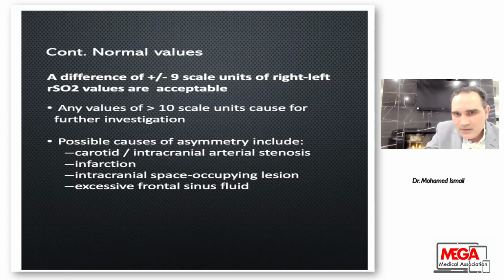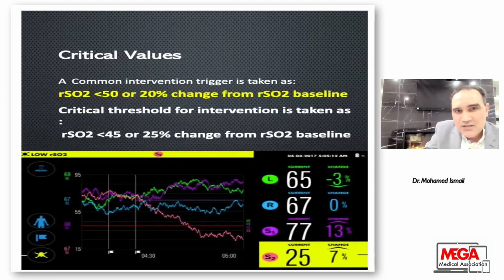That's why it is very, very important to have a baseline reading. Because if we miss the baseline reading while the patient is awake on room air, we will not appreciate the changes that happen after. If the patient has, for example, any stenosis in the brain arteries, the patient's baseline reading will be reduced. Then we will know that the reduction was already there from the beginning, not because of any intervention that we have done to the patient. Critical values: if the change is more than 20% or the number we get is less than 50, that is very important and we need to do something about it. The critical threshold is taken as less than 45 or more than 25% change from the baseline.